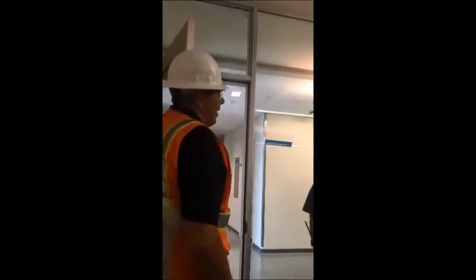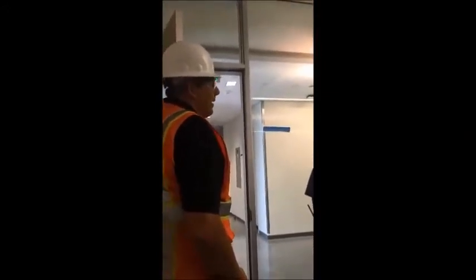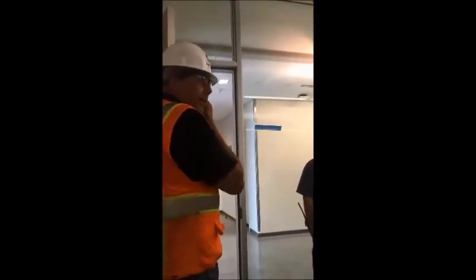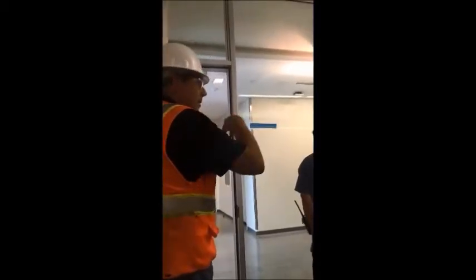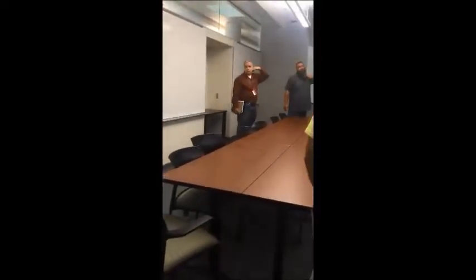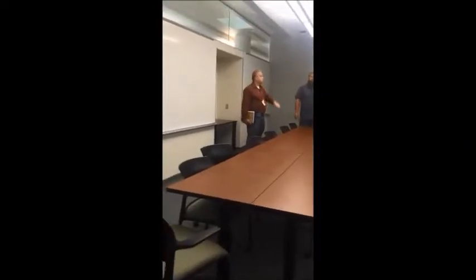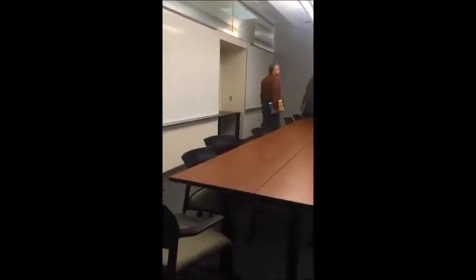The linear on the left hand side is basically a transfer that goes into the corridor. The idea is you'll push all the air in here, and then it'll go down the corridor. It just transfers over, it just loops over. Yep. So you keep the pressure a little bit higher here, and then the excess goes over. That's correct. So you don't have a return. Well, there is, just not in this space.